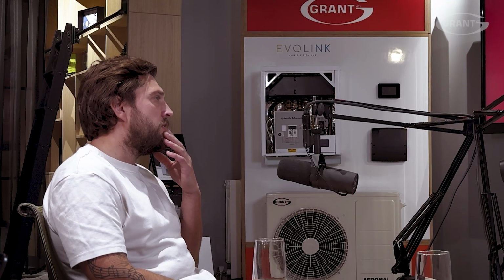So just going on from that, the Aerona smart controller, you were talking about having remote access. Most heat pump controls are weather compensated as well. Can you just explain to our audience what weather compensation is? Weather compensation is just a compensation control. Traditionally, you would have a fixed flow temperature, which would come out of the heat source all the time and never vary. Whereas in reality, when you're getting additional heat gains from external sources, you don't need that flow temperature constantly. As the weather changes, you'll need less heat in the house. As the weather cools down, you'll need more.